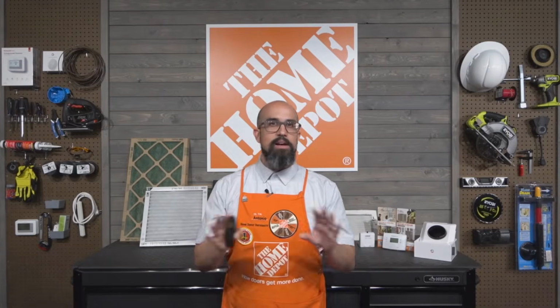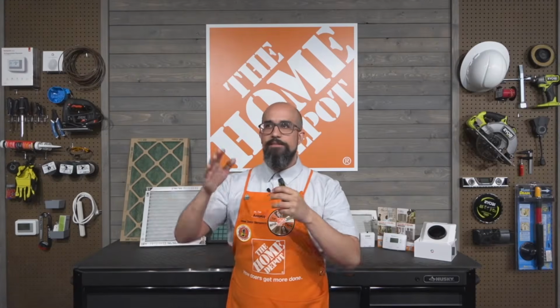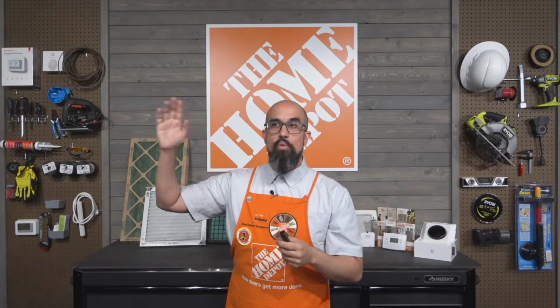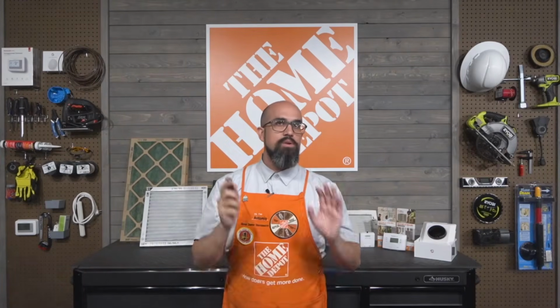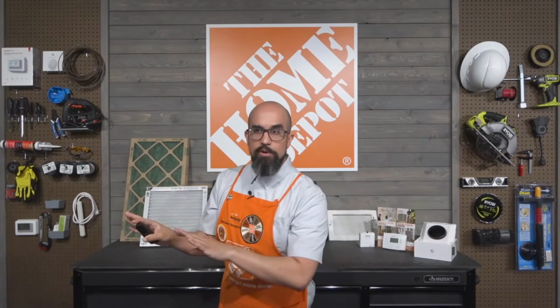For my friends in the Northeast especially, if you're dealing with severe winters with snow and ice buildup and want to cover the AC condenser unit outside, I'm all for it. Just keep two things in mind: if you cover it, make sure your system isn't set to an auto function, because if you go through an unseasonably warm winter and the AC kicks on while it's covered, that will damage your system. Also, if you don't have an auto feature, make sure you don't use the AC while it's covered. So just be mindful and proceed with caution if you're going to cover that condenser unit.